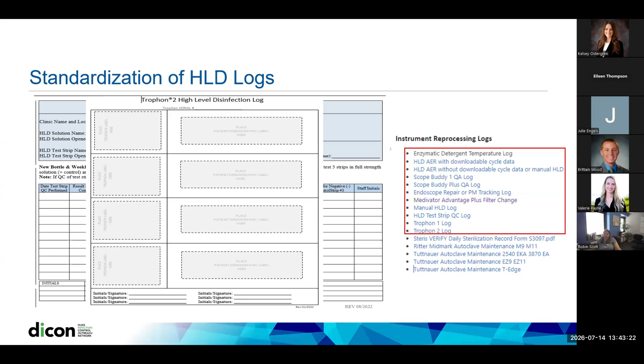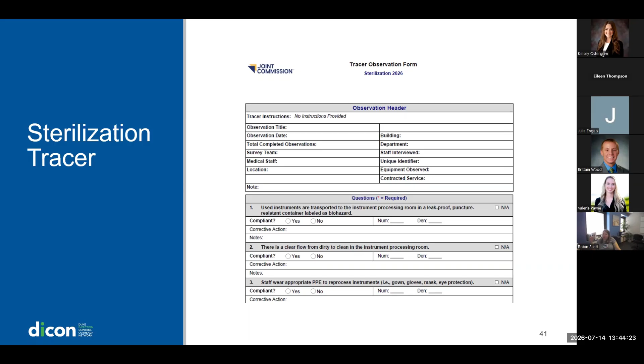So, like Valerie mentioned, in addition to our general IP tracer, we developed those two high-risk reprocessing tracers, one for high-level disinfection, and here we have one for sterilization. This is an example of that tool, and it again takes you step by step in tracing a critical device through each reprocessing step. This tracer tool is divided into sections just like previous ones, such as pre-cleaning, PPE usage, the reprocessing environment, instrument transport, manual cleaning, package and assembly of those instruments, sterilization wrap or containers, sterilization parameters, and quality control indicators such as your BIs and your chemical indicators, and then of course lastly with storage.